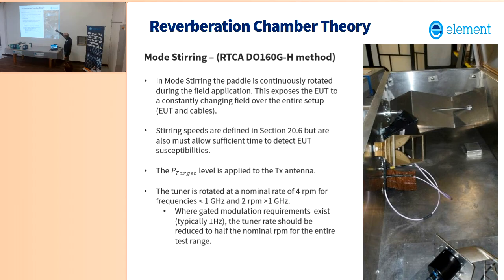Tuner speed for when you're doing mode stirred: if you're doing something that's gated, which a lot of these DO-160 tests are, with like a 1 hertz gating, on and off at a 1 hertz rate, then the guidance is that you should slow down the tuner accordingly. Typically cut the speed in half when you're doing that gating.